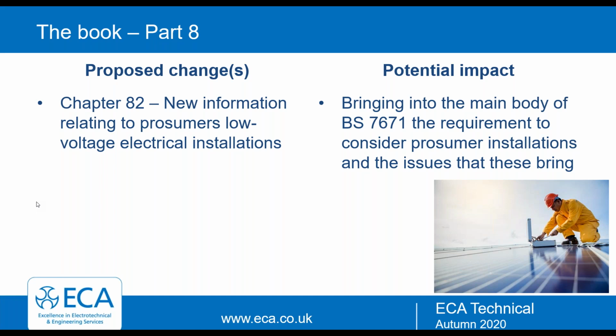There is a part of the reg that talks about where you've got surge protective or other devices likely to be damaged by the testing, where it's not practicable to disconnect them - e.g. a fixed outlet with an SPD in it. The test for that particular circuit may be reduced to 250 volt DC, but the insulation resistance shall have a value of at least 1 megohm. That's on page 232 of the regs, and it's been there for a while.